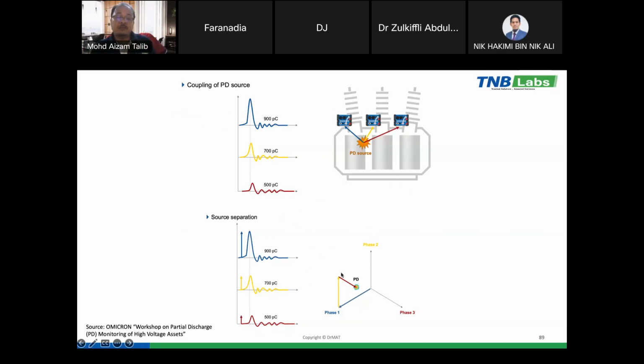So here, when we plot to these different clusters on phase 1, phase 2, phase 3, okay, here is how to understand. We know that PD at the blue phase has 900 picocoulomb, so we plot 900 picocoulomb. Then yellow is 700. Okay, this is for phase 2, yellow, this is 700. And then for the red phase it is 500. So this is the 500 of the red phase. So this is the cluster of the PD activities.